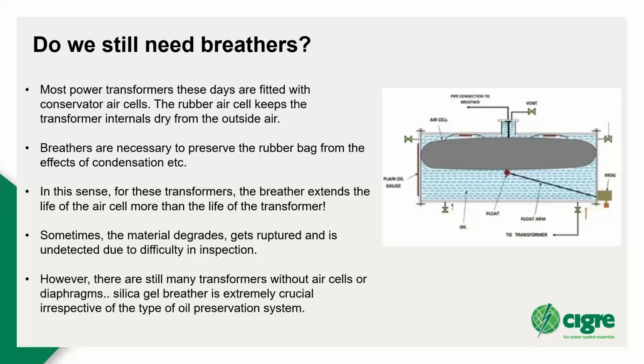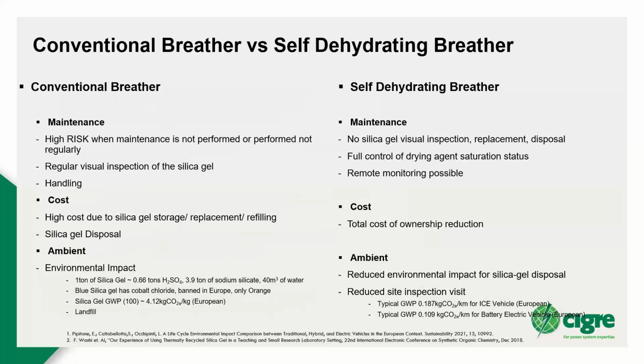Now, when we talk about the differences between the conventional breather and the self-dehydrating breather, there are some differences. First of all, maintenance: when we have a conventional breather, if maintenance is not performed regularly, there is a risk. You may have to do regular visual inspection of the silica gel and handling. Then there is recurring cost involved, because you need to store silica gel, replace it, refill it, and then you have the issue of disposal.